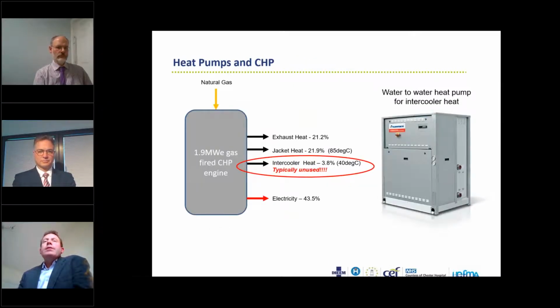But to make it work, they need to be absolutely super efficient, so we can look at using another heat pump here. CHP engines have an intercooler heat circuit which 99% of the time just goes through a rejection radiator because it's only 40 degrees C. We can integrate that with a water-to-water source heat pump to upgrade that intercooler heat to around 70, so we can put that back into our low temperature network as well. Next slide, please.